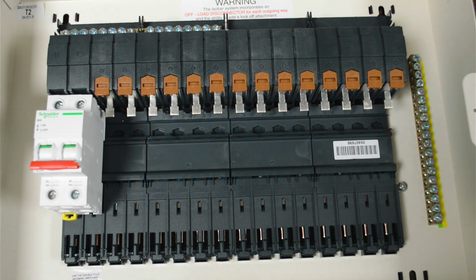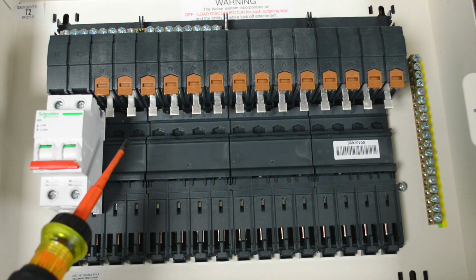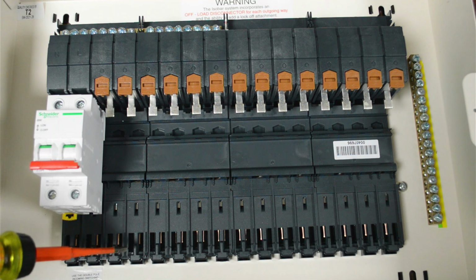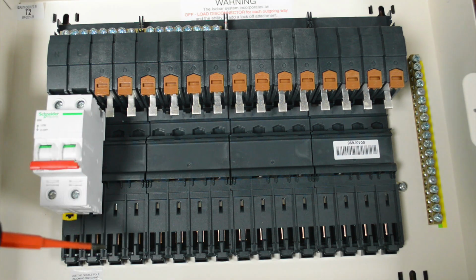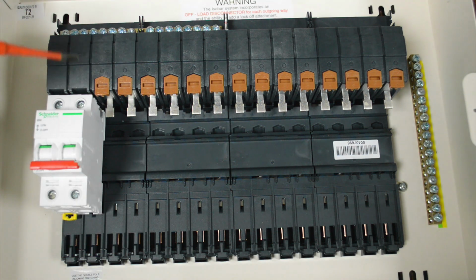And obviously you do also need your usual bars to connect conductors into. So as you can see up here with the neutral one, if you imagine this was just an MCB, for example, they don't have a neutral connection built into the overcurrent protected device, so you would still need to wire away as normal. Likewise for your CPCs as well, they still need a point of termination within the enclosure itself.